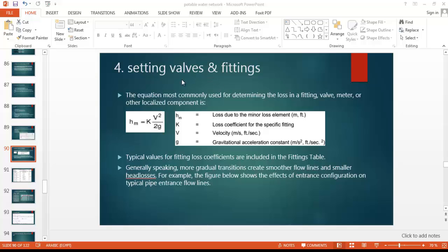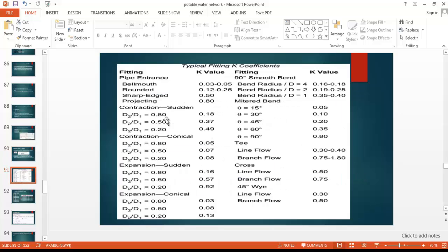We will discuss setting the valves and fitting coefficients inside the network to have the ability for calculating the minor losses due to fitting valves, fittings, or other localized components. First, we will discuss the formula used for calculating the head loss coefficient. The head loss coefficient equals the loss coefficient for the specific fitting multiplied by the velocity head, which is the fluid velocity squared divided by two times gravitational acceleration.